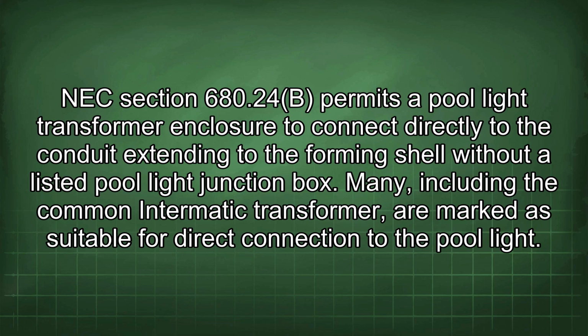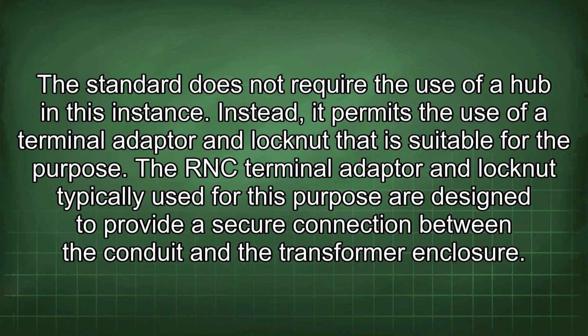NEC Section 680.24(B) permits a pool light transformer enclosure to connect directly to the conduit extending to the forming shell without a listed pool light junction box. Many, including the common Intermatic transformer, are marked as suitable for direct connection to the pool light. The standard does not require the use of a hub in this instance. Instead, it permits the use of a terminal adapter and lock nut that is suitable for the purpose.